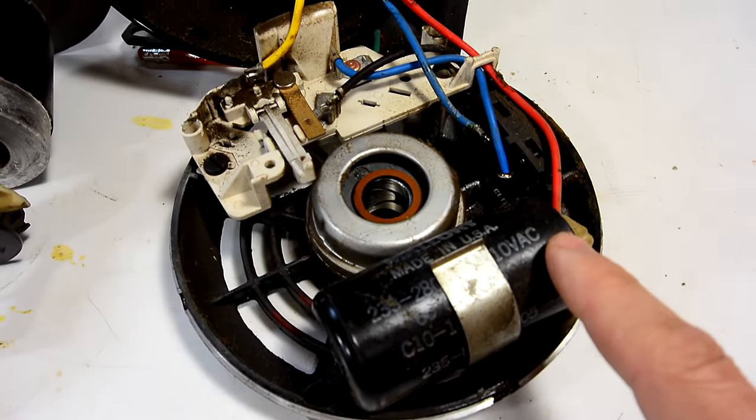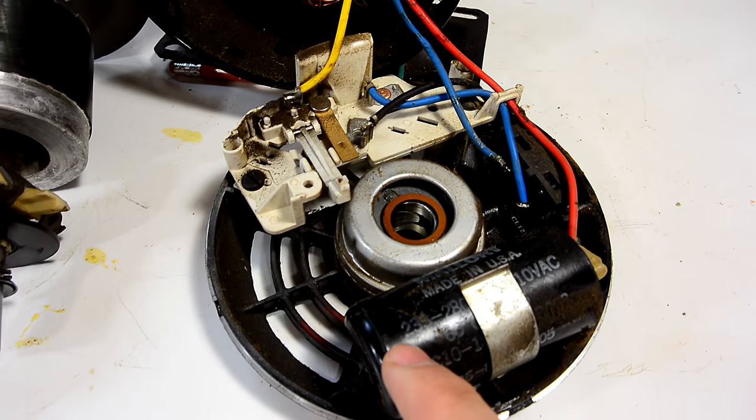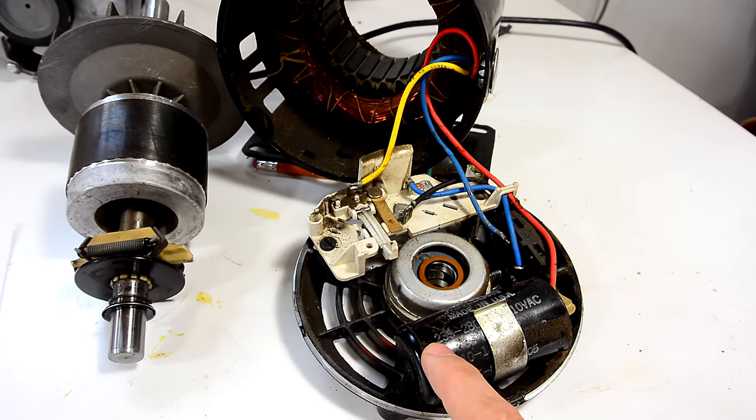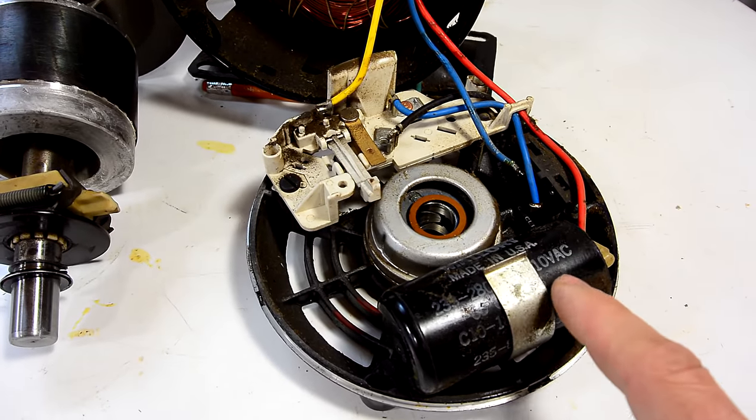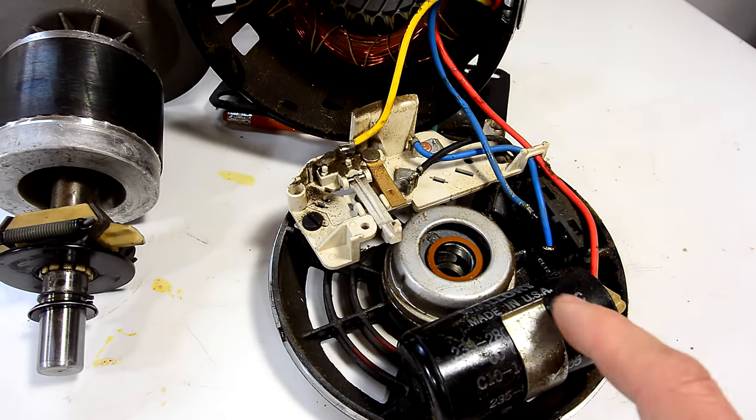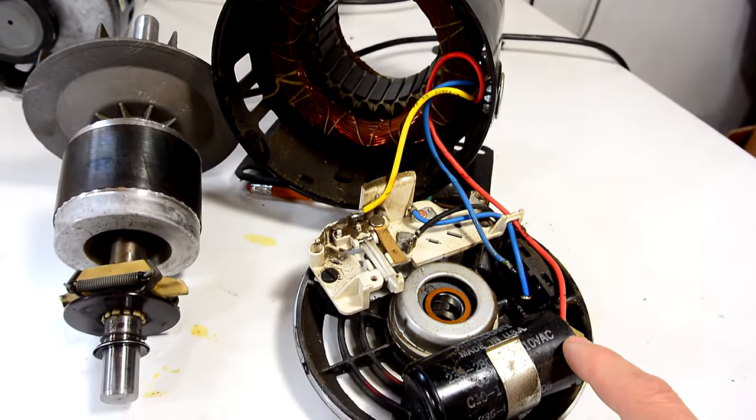If the starter winding helps to create a rotating magnetic field to spin up the motor why disconnect it once the motor's actually up to speed? The whole phase shifting to starter winding with the capacitor is not as elegant as it would sound. The size of the capacitor very much depends on the expected load of the motor and if we just connect it briefly temporarily at the start it doesn't matter if it's a little bit inefficient or the wrong size because we won't leave it engaged.